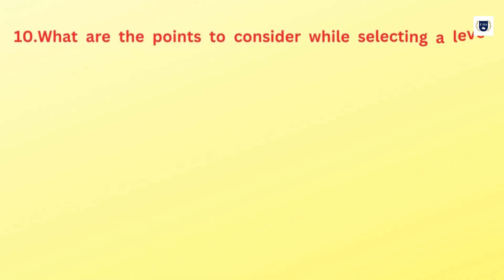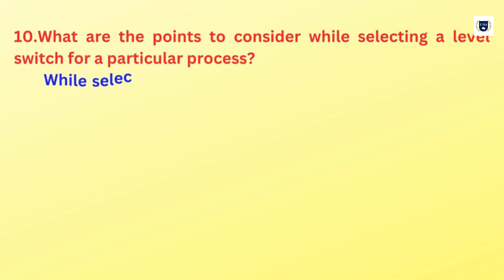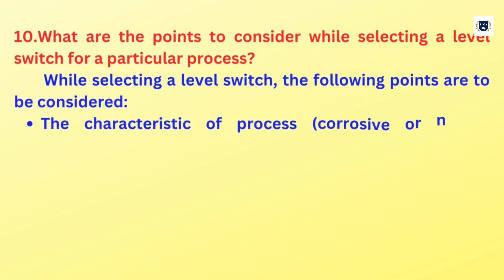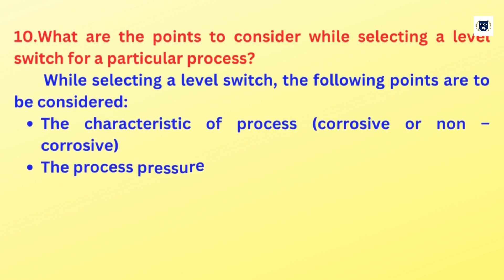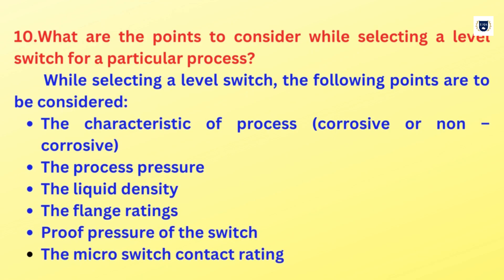What are the points to consider while selecting a level switch for a particular process? While selecting a level switch, the following points are to be considered: the characteristic of the process (corrosive or non-corrosive), the process pressure, the liquid density, the flange ratings, the proof pressure of the switch, and the micro switch contact rating.